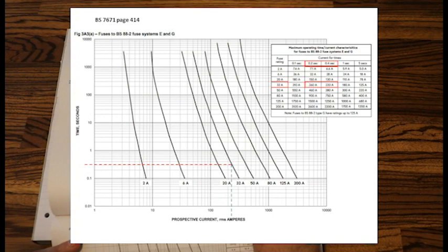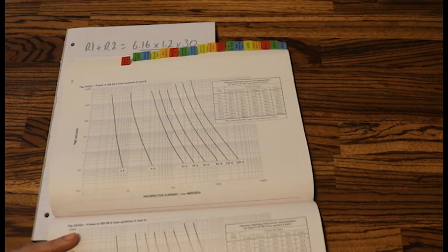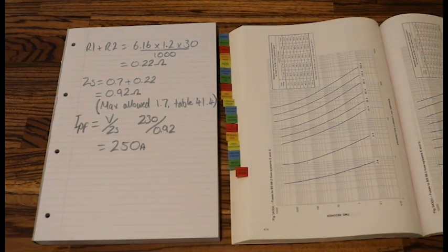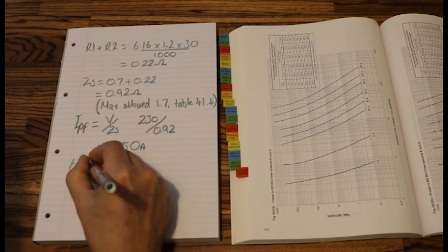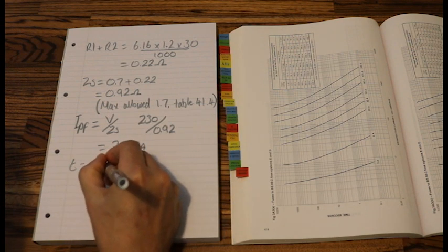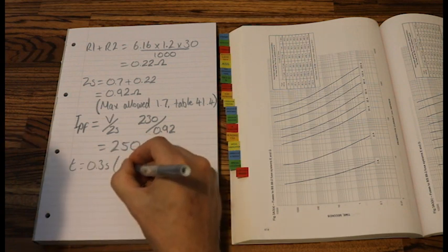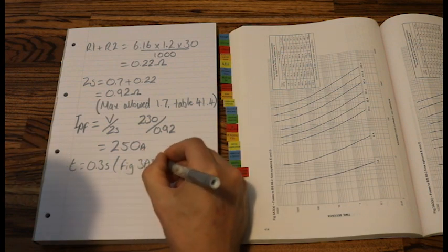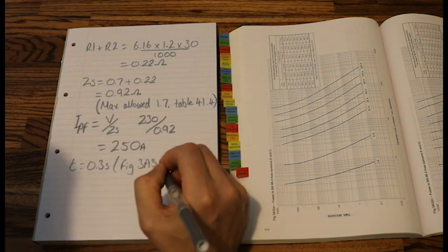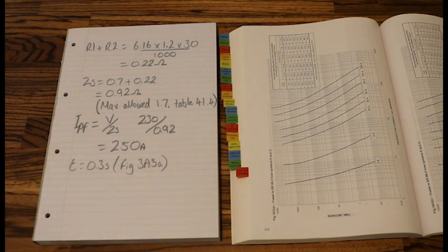So I would say in between that, safe to say that my T, my disconnection time, would be 0.3. So my T value equals 0.3 seconds. And that was from figure 3A3A. So what is the maximum time that I'm allowed? Is it less than 0.3 or is it more than 0.3?